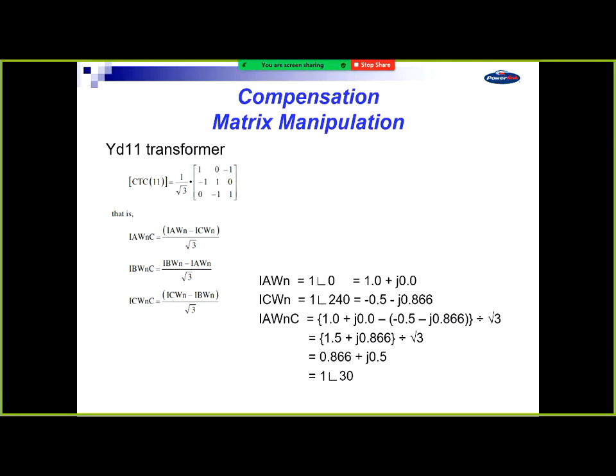Your A-phase is 1 angle 0. Your C-phase is 1 angle 240. You subtract them, you're going to come up with that value of 1.5 plus J 0.866. You divide that by √3, you come up with 0.866 plus 0.5. Put that back to polar, you get a 1 angle 30. So A phase going through a YD11 transformer is going to be shifted because the 11 is a minus 30 degrees.